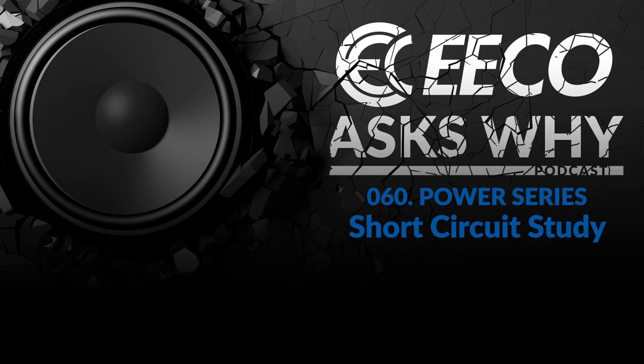And as new factories get put in place and utility demands change, the Thevenin short circuit values increase over time. When they increase, obviously the amount of short circuit current into the system increases as well. So for that reason, it's recommended every 3 to 5 years, with 5 years being the maximum to have a short circuit study done. That's probably the general answer to your question.